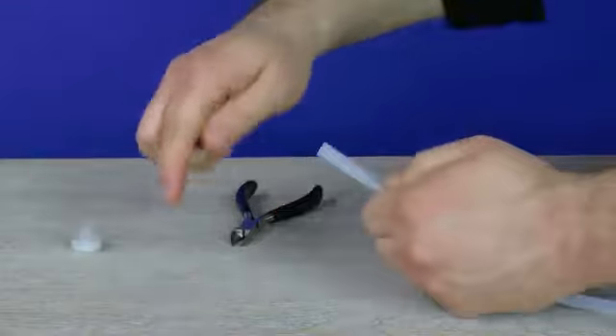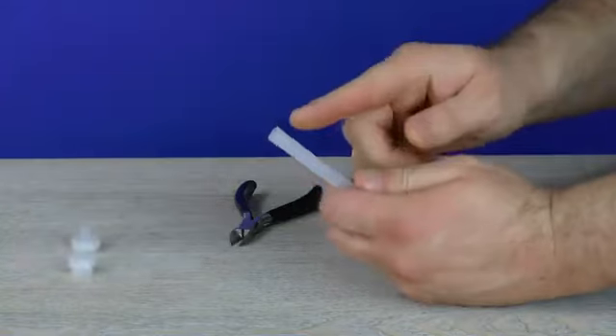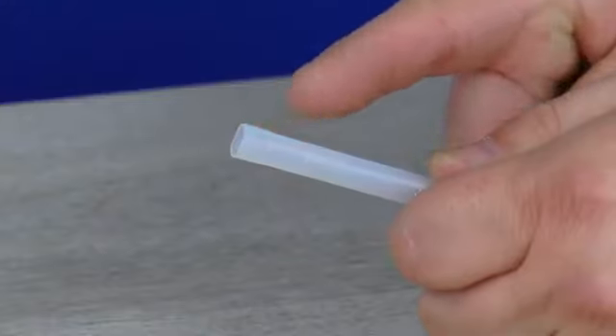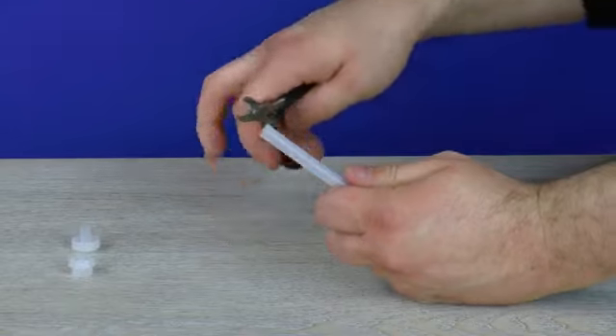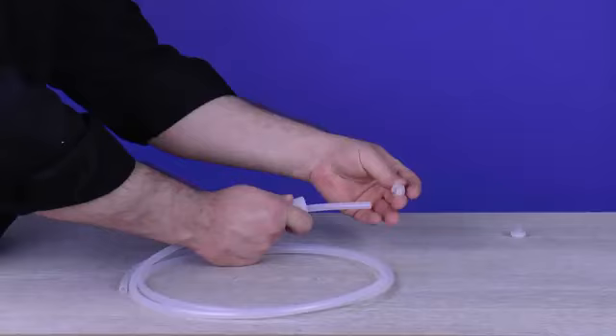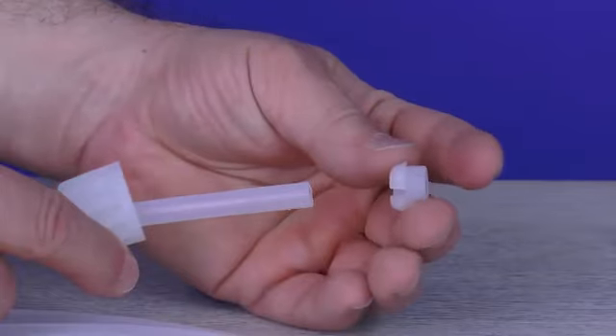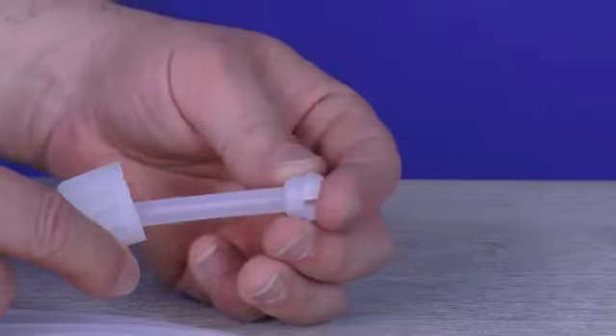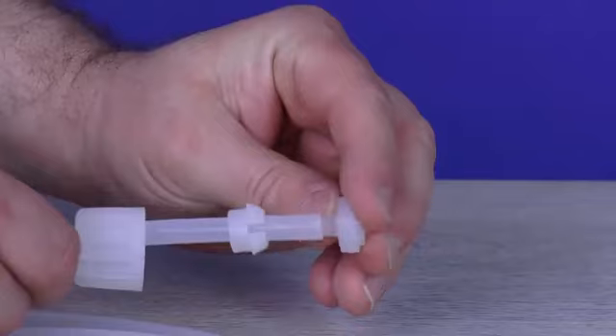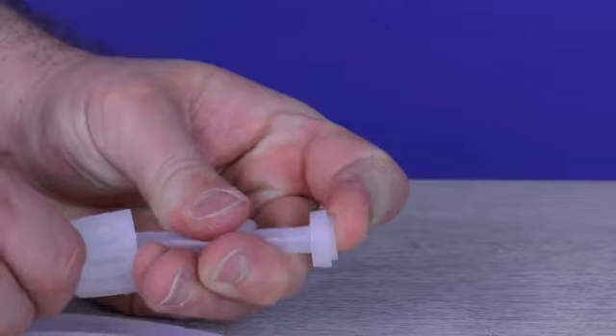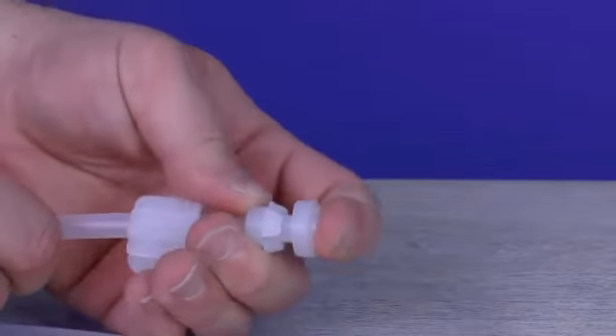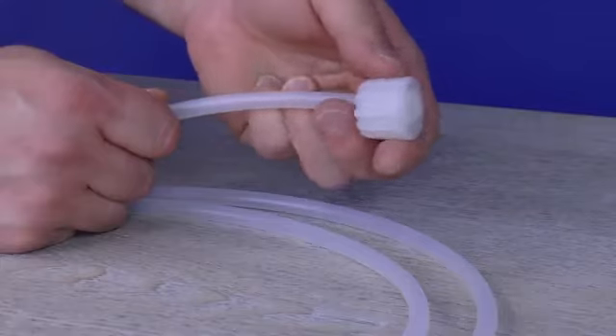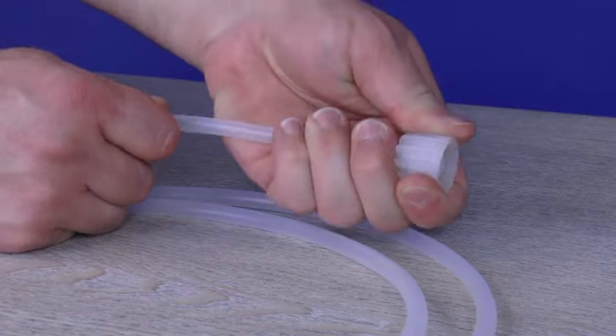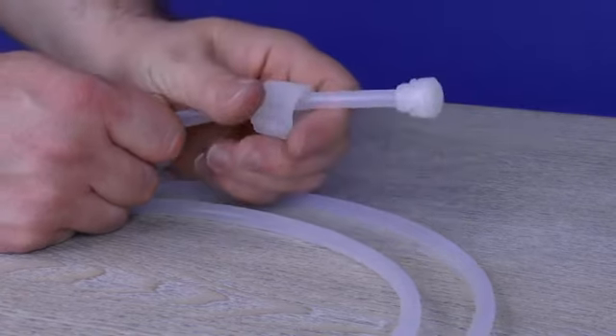Remove the nozzle and collar from the tube and set aside. Do not lose them. Look at the end of the tube. If the tube's end is flared, use the diagonal pliers to cut the flared portion off. Slide the collar back onto the tube and make sure the collar's crown is pointing away from the tube nut. Slide the nozzle back into the tube's opening. Push the collar and nozzle together as close as possible. Pull the tube nut toward the nozzle to compress the collar and nozzle tight together, forming a ferrule connection.